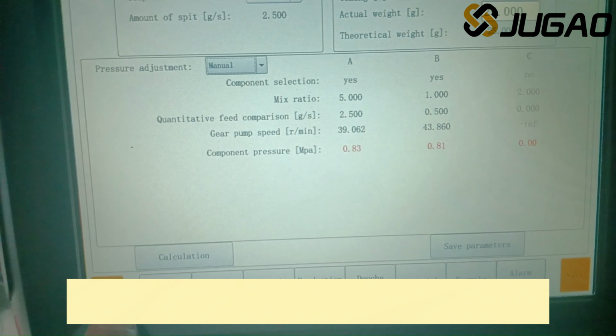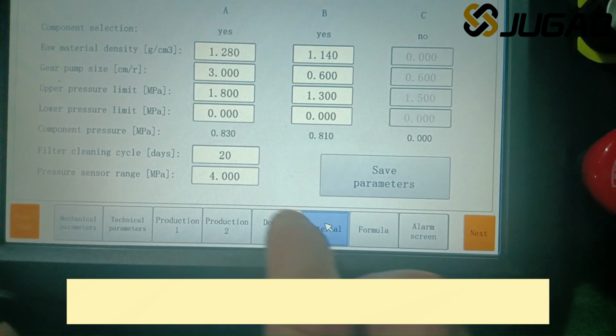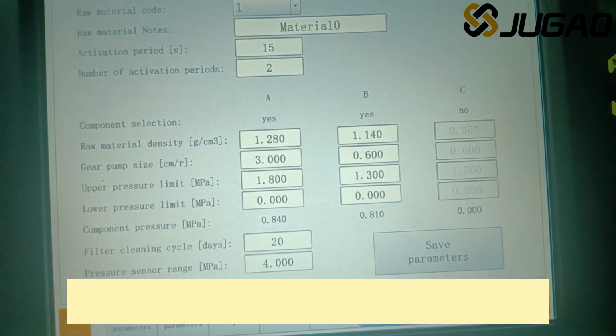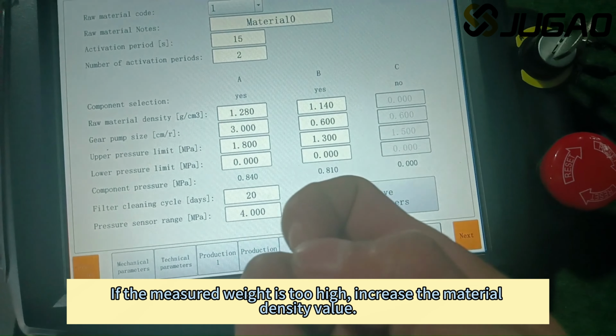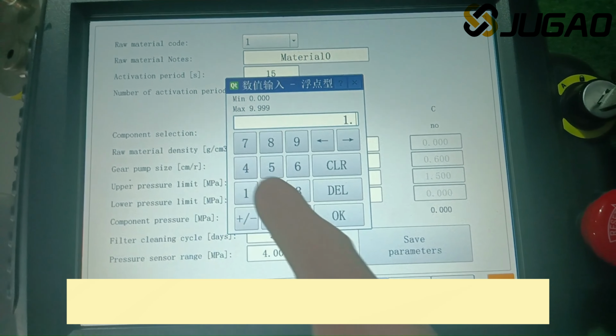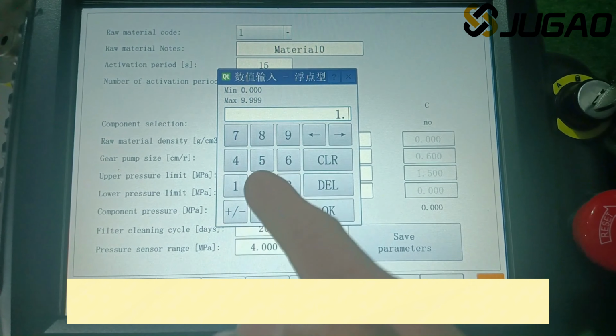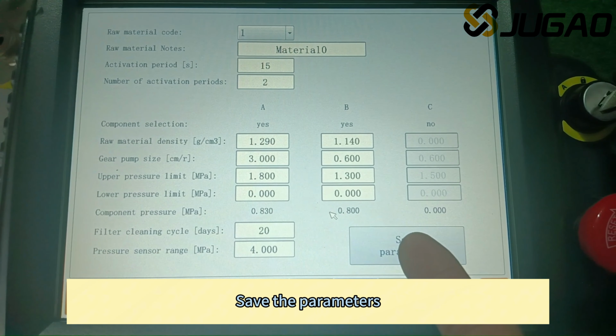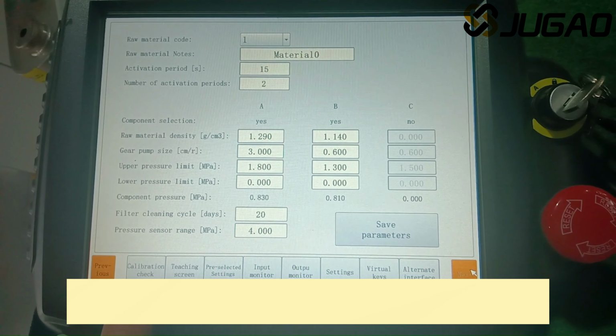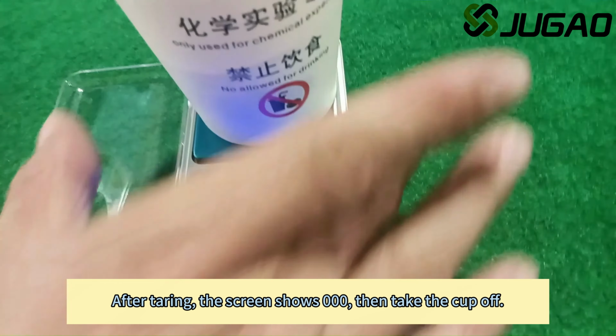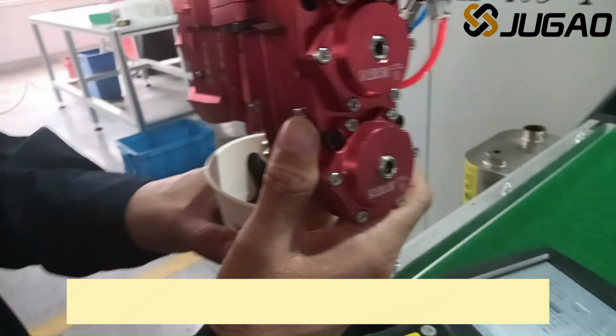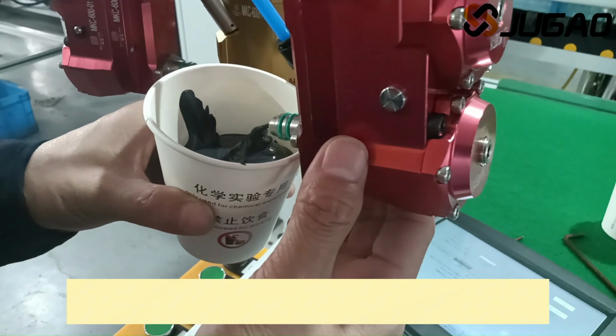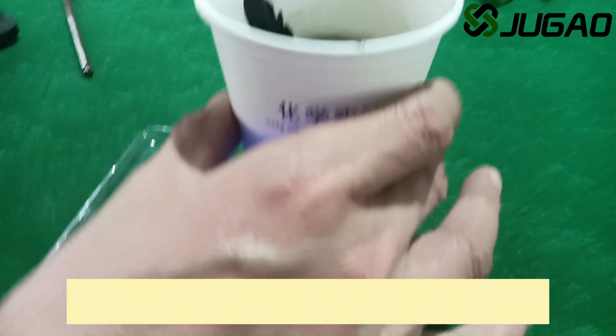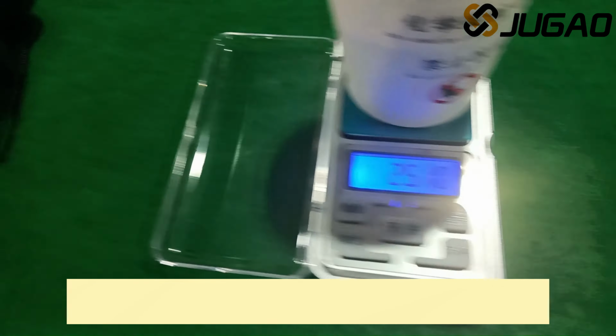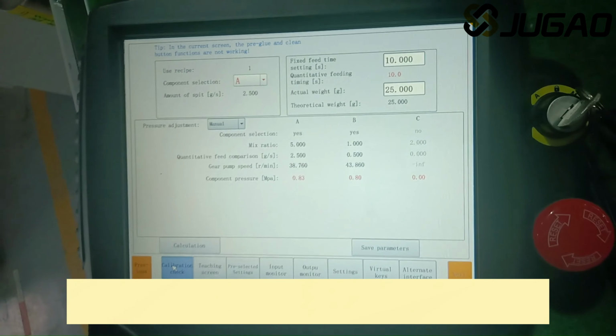Select previous page. Select material. We can adjust the density parameter of material A or B. If the measured weight is too high, increase the material density value. Save the parameters. Choose the next page. Calibration check. After taring, the screen shows 000, then take the cup off. Then put it on top. 25.1. 0.1 more. This is no problem.